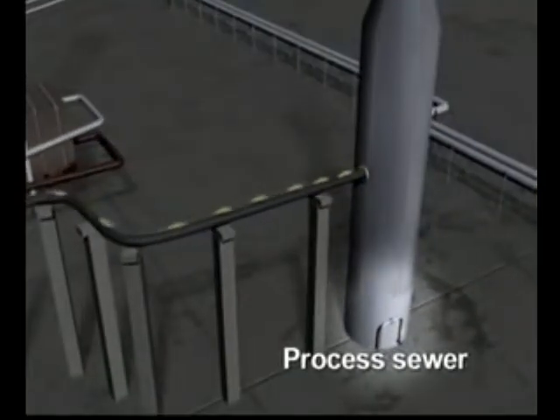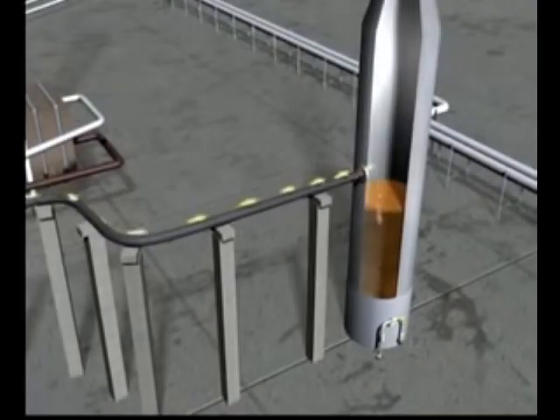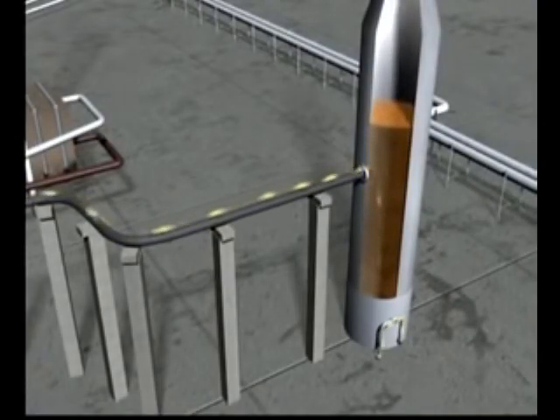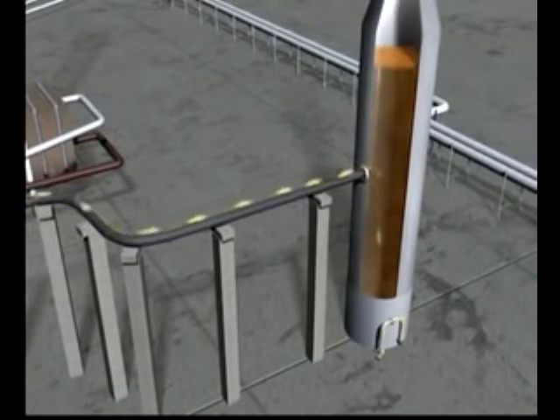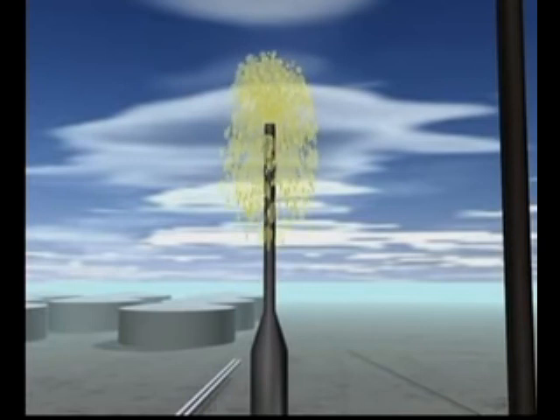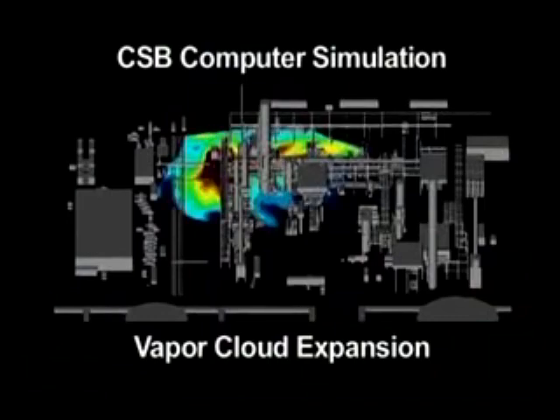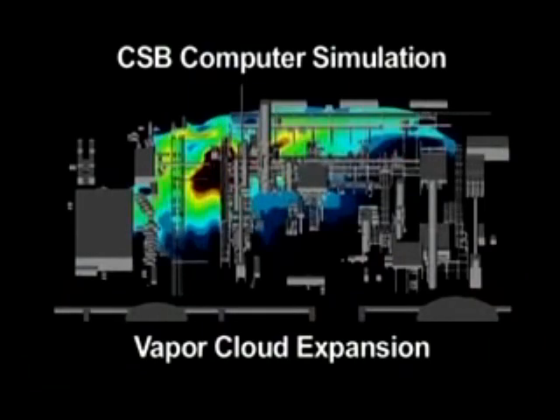Some liquid overflowed from the blowdown drum into a process sewer, but the high-level alarm on the blowdown drum didn't go off. The drum filled completely, and bystanders saw a geyser-like eruption from the top of the blowdown stack. The eruption lasted about one minute. Liquid fell to the ground, creating a large, flammable vapor cloud. This model predicts how far the vapor cloud expanded across the area just one minute after the release began from the stack.